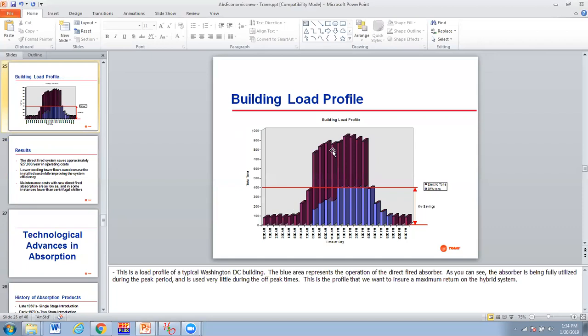Up to the top, that's the total load on the building as a function of hour of day. This is during the summertime, where this is the on-peak period. The on-peak period is noon to 8 over here. And so we're going to run the absorber from 8 a.m. until 8 p.m., but it's going to be fully loaded for all of the on-peak, when there's more load than that. And when the load falls off, obviously we won't have to produce as much refrigeration. The blue here is the amount of the load that the absorber is going to provide, and the overall peaks here are the total cooling load.